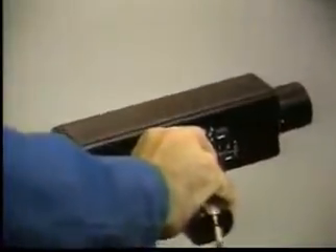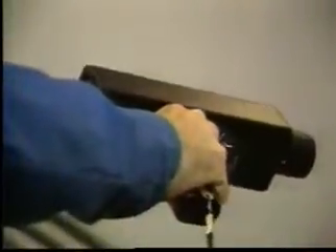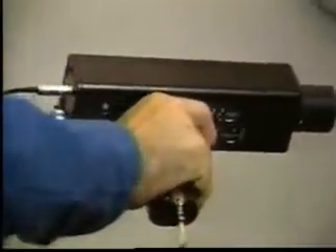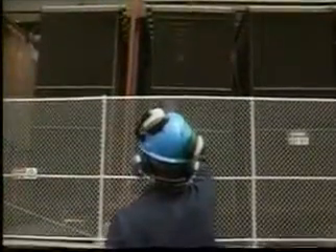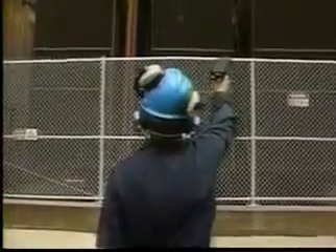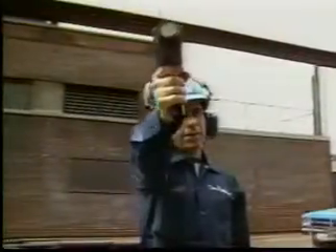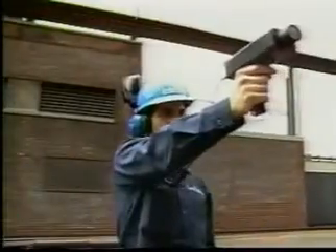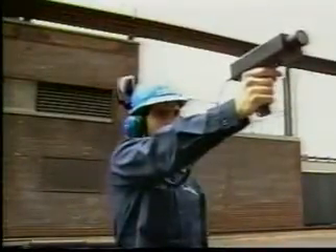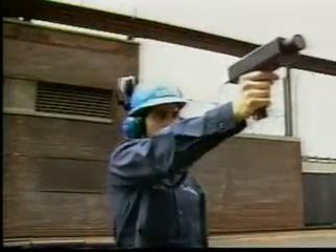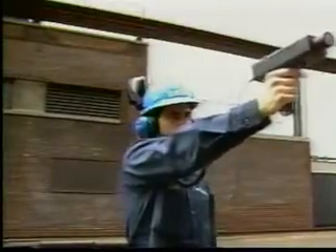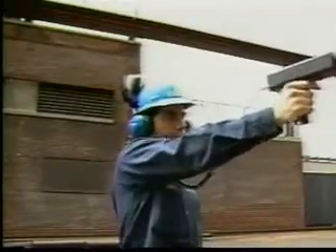These techniques can be applied to all types of leak detection problems. Most of the standard techniques apply even to detecting electrical leakage, both arcing and corona. Electrical leaks make a frying or buzzing sound. When scanning high voltage lines or transformers, be sure to follow your standard safety procedures.